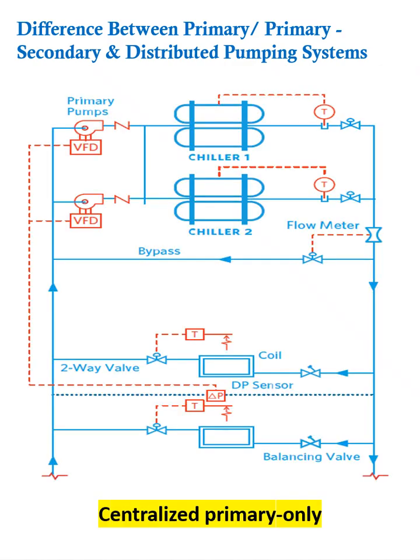We will discuss the difference between primary variable, primary secondary, and the distributed pumping system for chilled water applications. Here you can see there is a plant room, and this plant room is connected with the primary variable pump where the VFD has been integrated to the primary pump. The chilled water is being pumped with both of these pumps to the load side, which is the air handling unit or the coil. This typical arrangement is called the centralized primary variable system.